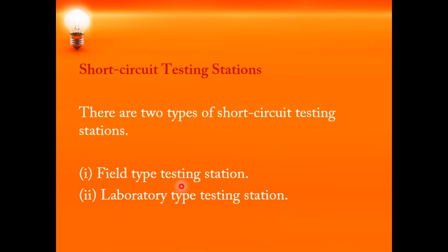Say you are going to test the circuit breaker for research purposes. Research purpose means, okay, one trial you didn't get, you go for another trial. If you keep on repeating, this would be a problem for the actual electric supply, right? Because you are interrupting the actual existing supply. So say you take an example of a substation where you are going to test the circuit breaker. If you keep on testing the circuit breaker, what is going to happen? The power is going to get interrupted. That is why in the field type testing station, you can test one or two circuit breakers, but you cannot keep on testing the circuit breakers frequently. That is one disadvantage.